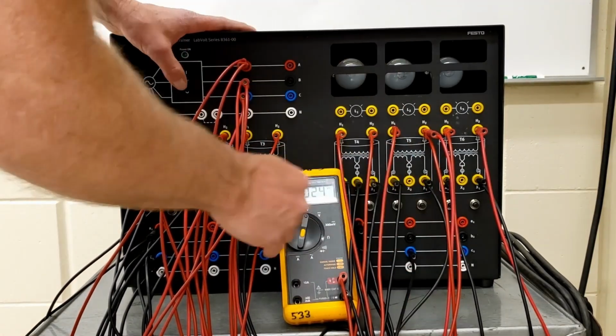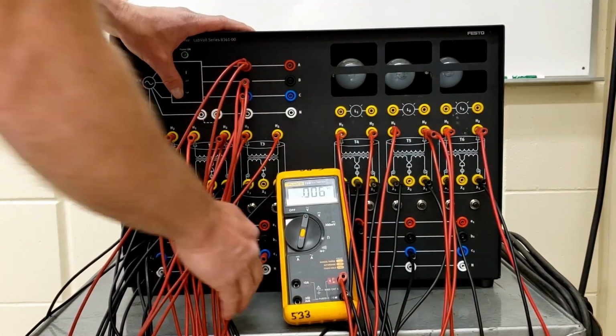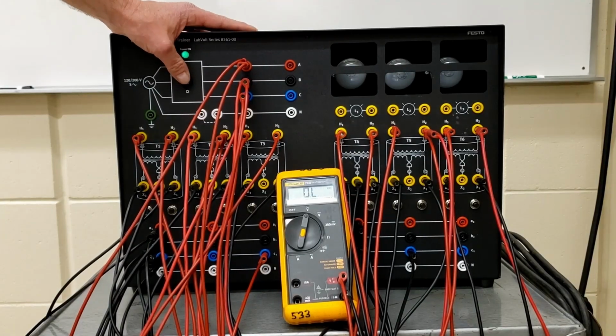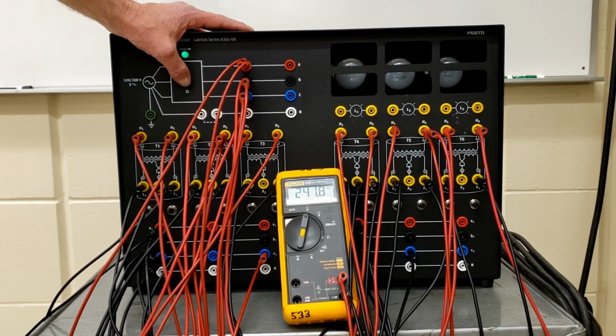Between C1 and C2, this will be interesting to see whether we have a higher voltage here. C1 and C2, we got 240 volts between those. So basically 138, 140 between A1 and A2, 140 between B1 and B2, and now between C1 and C2 we're seeing 240 volts.